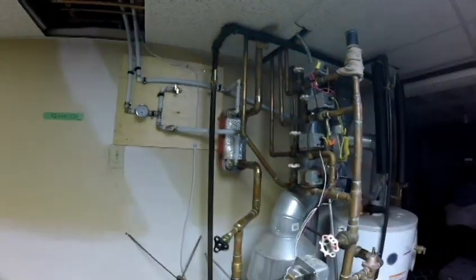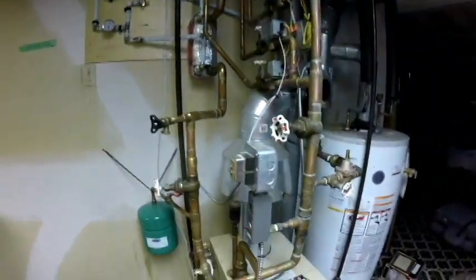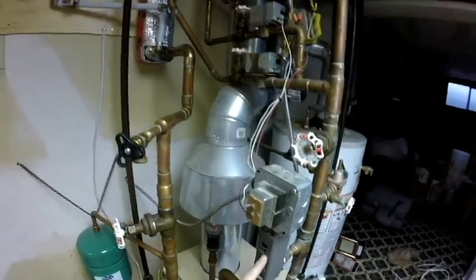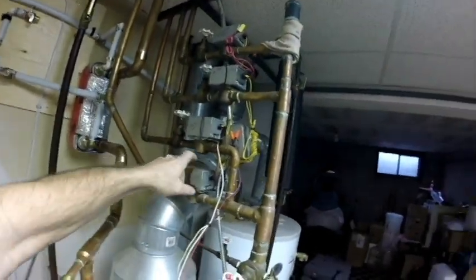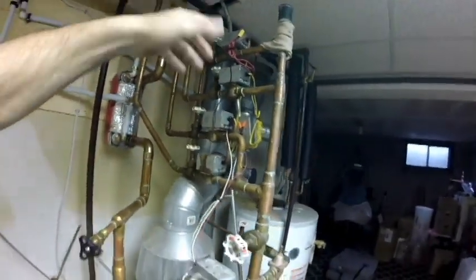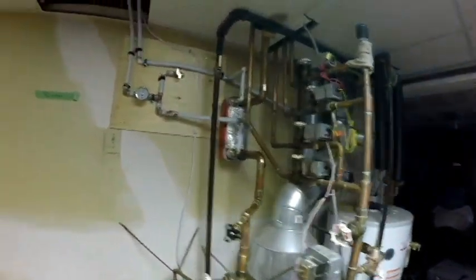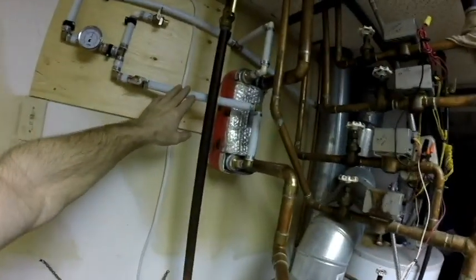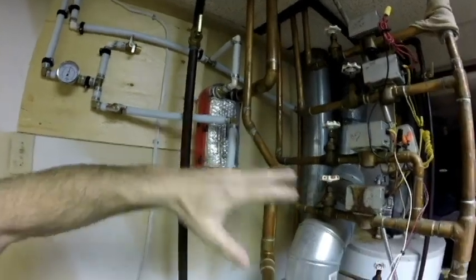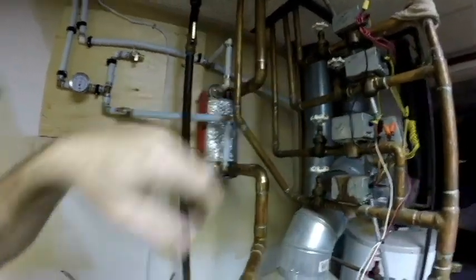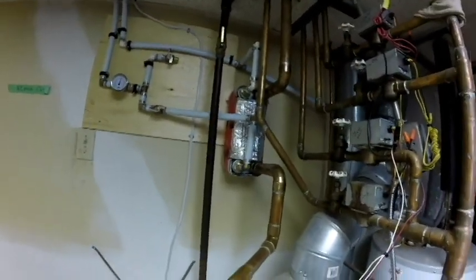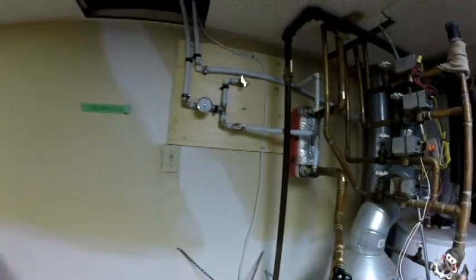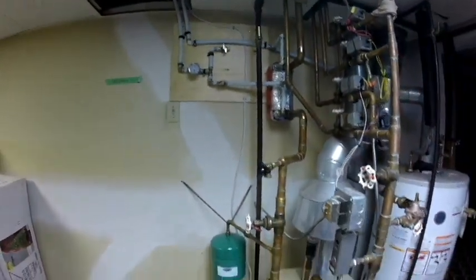Then this will be controlled by an electronic zone control valve, which is basically the same thing you have in your interior house. You have these zone valves which heat the 4 different zones in my house. This is going to have 2 zone valves, one to heat this zone and the other to heat that zone. I'll probably end up putting in a 3rd zone because I eventually want to use this to heat my hot tub outside as well. So yeah, there you have it.